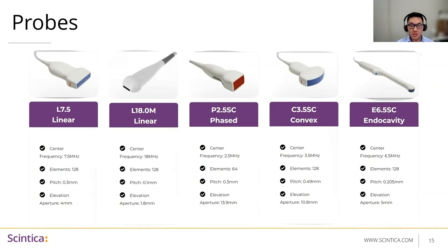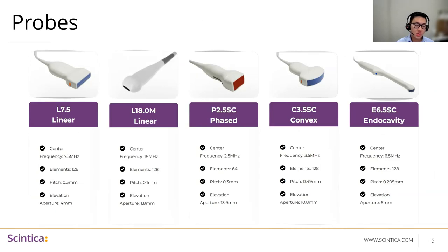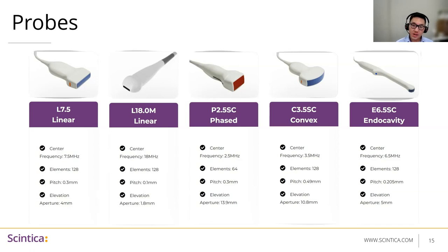Standard probe options available for purchase work right out of the box with matching pinout. These include two linear array options, a phased array, a convex, and an endocavity probe. They range from 64 to 128 elements with frequencies from 2.5 megahertz up to 18 megahertz, and the maximum transmit frequency for the system is 30 megahertz. If you already have your own transducer, as long as you provide the pinout, an adapter board can be made and it would work seamlessly together.